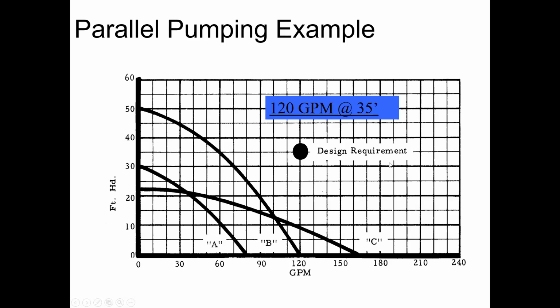Here's a real simple, quick example. The conditions are, I need, say, 1,200,000 BTUs for a heating application. And that's where I got the 120. I designed it on a 20-degree delta T. And when I did my calculation, I got about 35 feet of head loss to overcome to get that appropriate flow out to the building. And I'm looking at, say, some stock pumps, wholesaler, rep, whatever. Obviously, in this example, nothing falls within the conditions that I want. But hey, I've got 2 smaller pumps, and if I put them in parallel, I can get you there. So what do I look at?